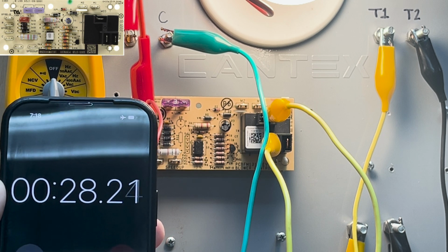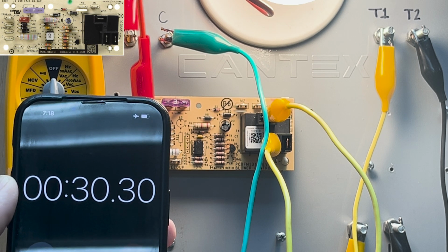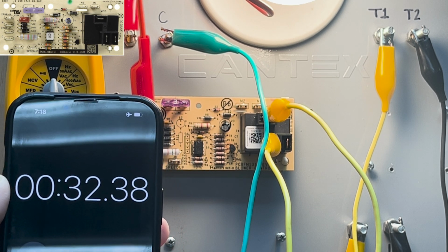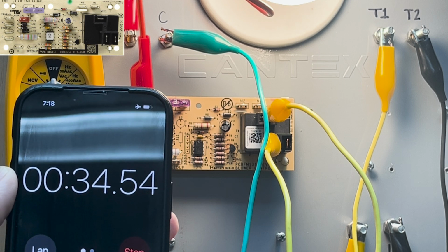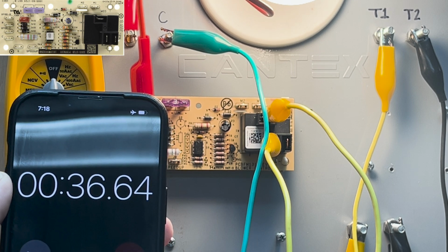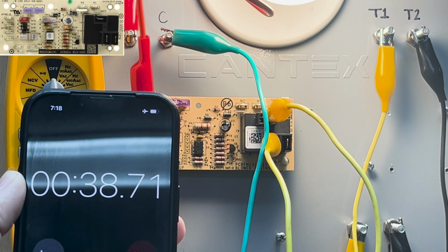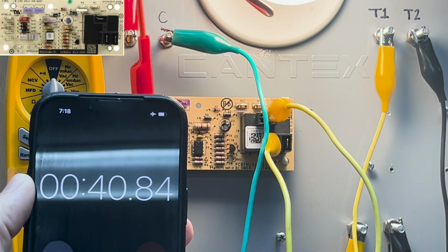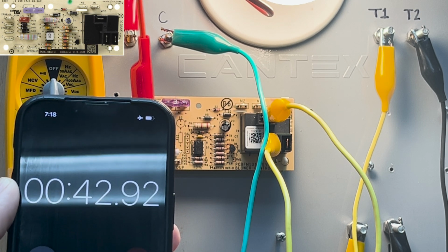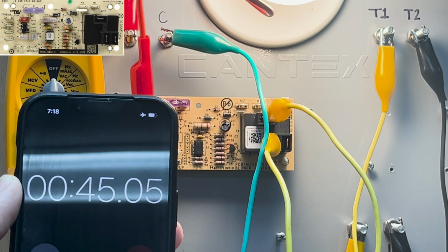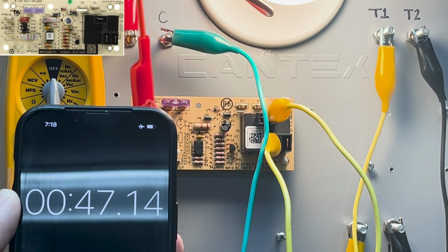Also, if you're not getting a G call, you want to make sure that you give it a G call, take the G call away, start your timer, and if you're running on and on for a minute, 5 minutes, 10 minutes, you obviously have a bad board. You just need to replace that control board.